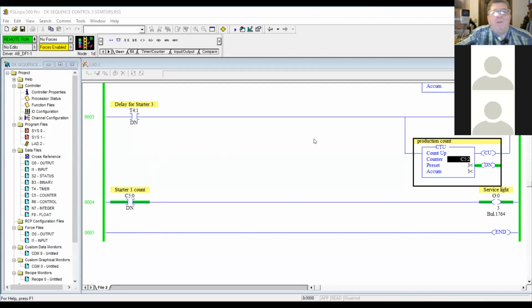Most of the time when you're online with the older PLCs, it's going to be a serial cable. So you would be dealing with the RS-232 driver in Links, not the Ethernet driver, unless you happen to have one that somehow had that. I hadn't seen any of the older ones that had Ethernet on.